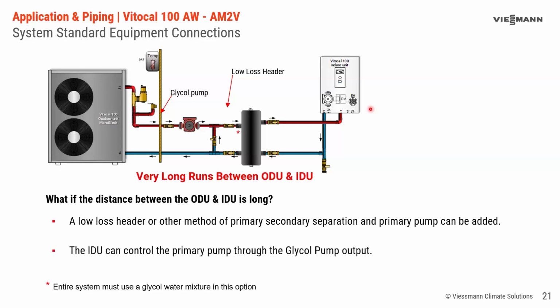So again, to control this pump, we're still going to use the pump output. I see my arrows have moved. The pump output to the pump from the glycol output. So it's still called glycol pump in the unit, still does the same function, except we're going to be all glycol in this as opposed to separating it with the heat exchanger. The entire system is glycol in this application, and it was boiler water on one side of the plate exchanger.